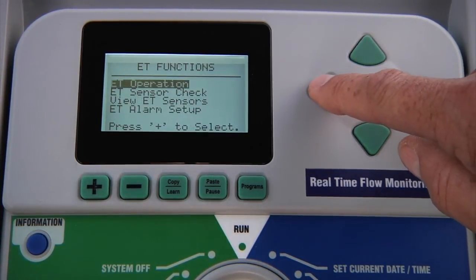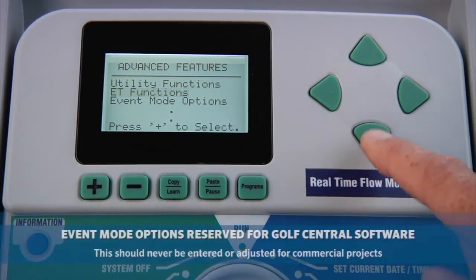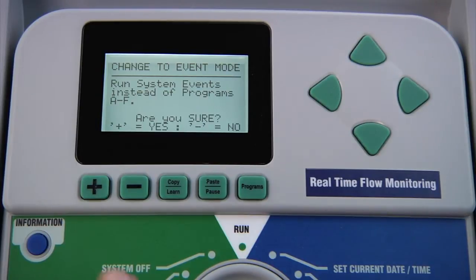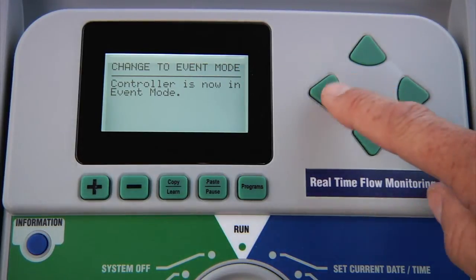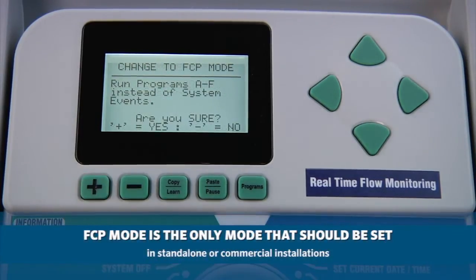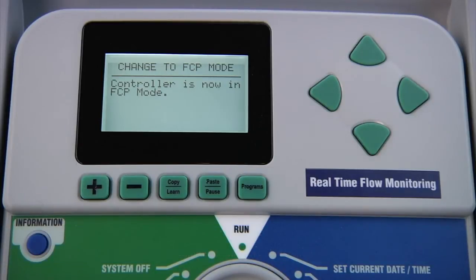Back at the advanced features main menu, the next function is the event mode options. This feature is reserved for golf central software and should never be entered or adjusted in commercial projects. If the screen ever says event mode, the controller will not irrigate normally. If a controller has been set to event mode, the normal operating display in the run position will say system event mode on. This must be changed back to FCP mode for normal watering to resume. The normal operating mode of the controller is FCP or field controller program mode, and this is the only mode that should be set in standalone or commercial installations.